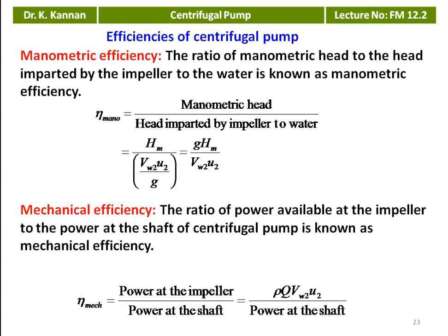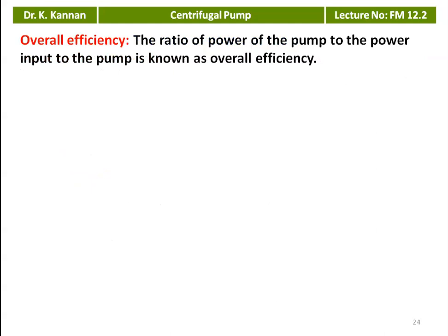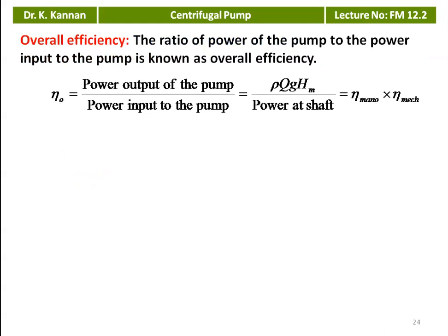Mechanical efficiency is the ratio of power available at the impeller to the power input to the shaft: η_mechanical = power at impeller / power at shaft, where power at the impeller equals ρ·Q·Vw2·U2. Power at the shaft is the power given to the pump by the electrical motor. The overall efficiency is the ratio of power output of the pump to power input to the pump: ρ·g·Q·Hm divided by power at the shaft, which equals manometric efficiency multiplied by mechanical efficiency.